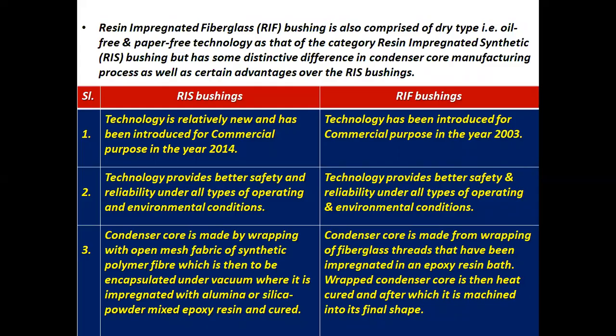Now, resin impregnated fiberglass bushing is also a dry type, that is oil-free, paper-free technology, like the resin impregnated synthetic bushing, but has some distinctive differences in the condenser core manufacturing process as well as certain advantages over RIS bushings. Let's see the difference between RIS bushings and RIF bushings, that is resin impregnated fiberglass type bushings.